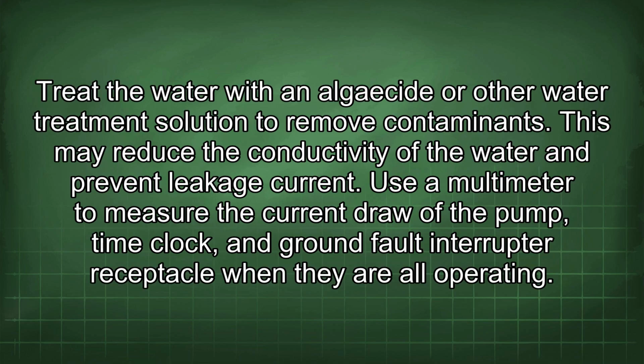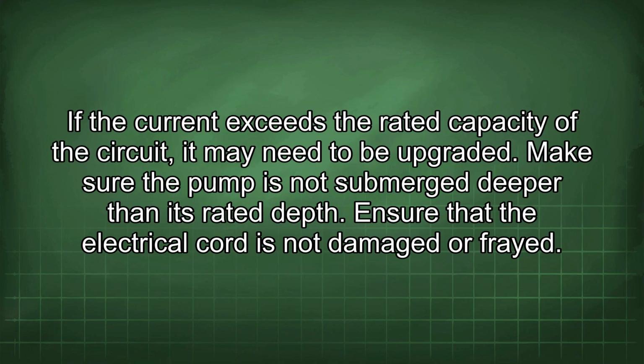Treat the water with an algaecide or other water treatment solution to remove contaminants. This may reduce the conductivity of the water and prevent leakage current. Use a multimeter to measure the current draw of the pump, time clock, and ground fault interrupter receptacle when they are all operating. If the current exceeds the rated capacity of the circuit, it may need to be upgraded.